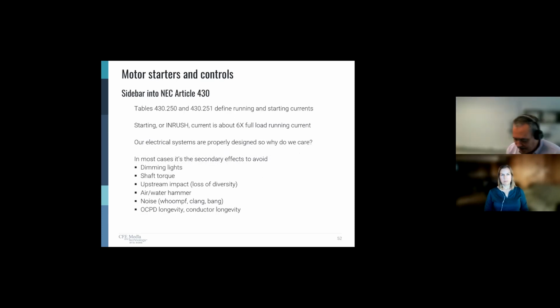So how do we start these things? How do we control them? Well, we have motor starters, we have motor controls. And now we get to talk about the National Electric Code, Article 430. If you're dealing with motors, you will spend a lot of time in this article, so it will become your friend. Tables 250 and 251 talk about running and starting currents for various sizes of motors, and they talk about inrush current, which currently is about 6x of full load running current per the NEC. A lot of manufacturers will give you a starting full load current.